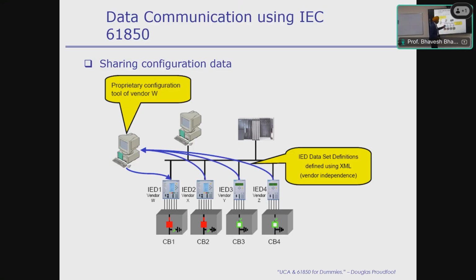So for example, one of the IEDs goes bad. Its functionality can be transferred to another IED or a spare IED, and you can do that through configuration. Because remember, logical nodes are the ones that provide functionality to any IED. So if you can just change the logical node, then you can change the functionality.